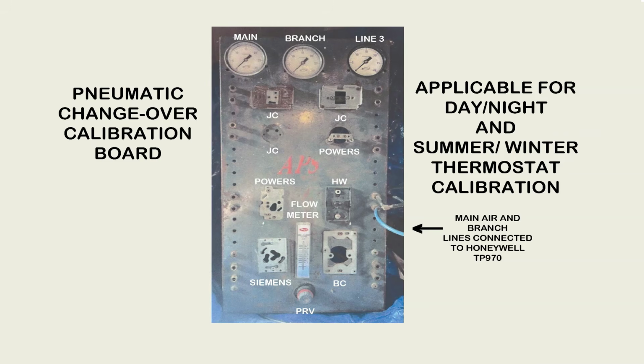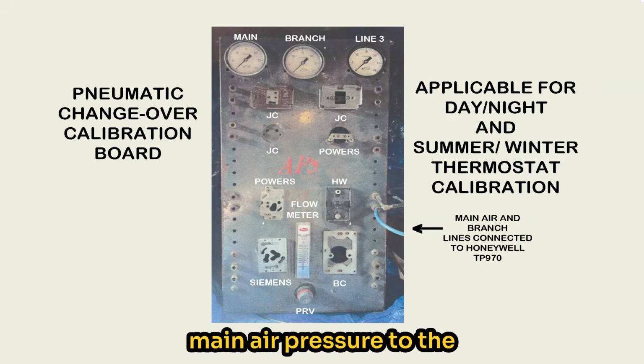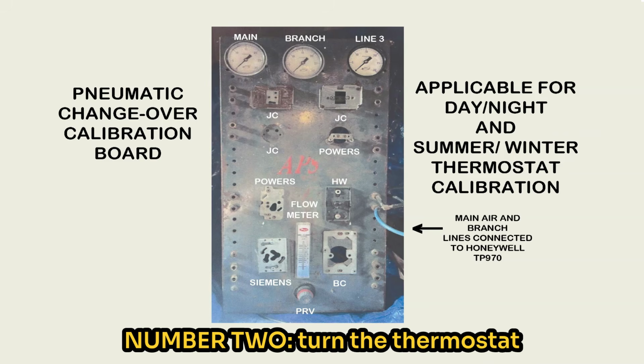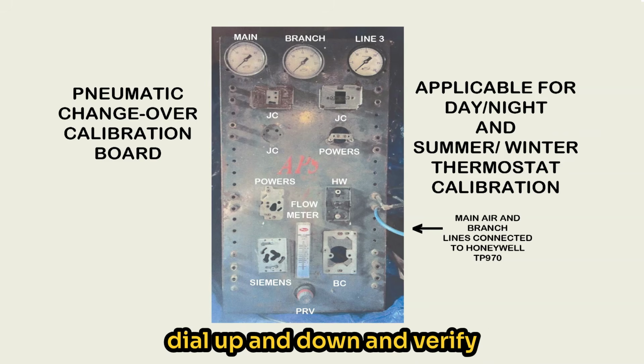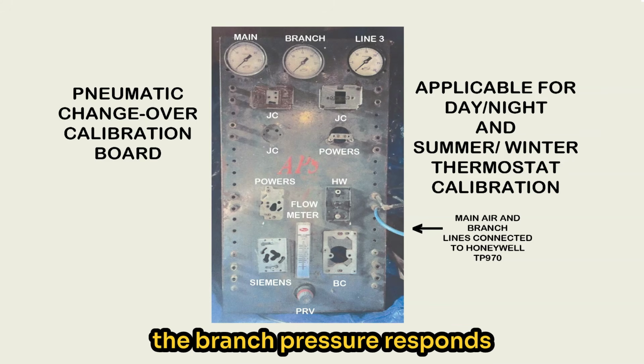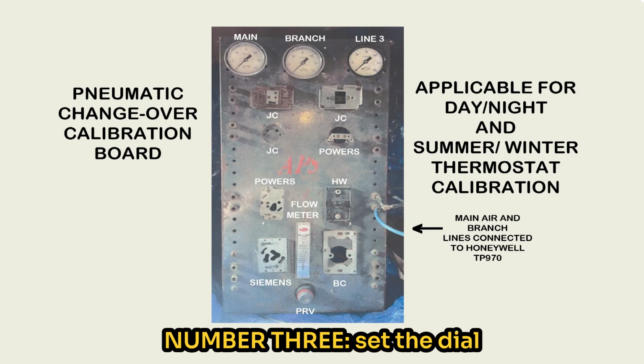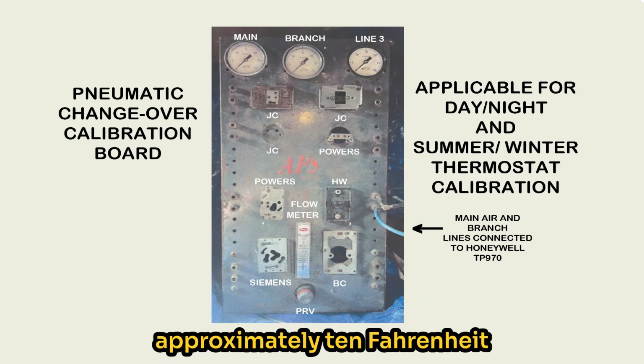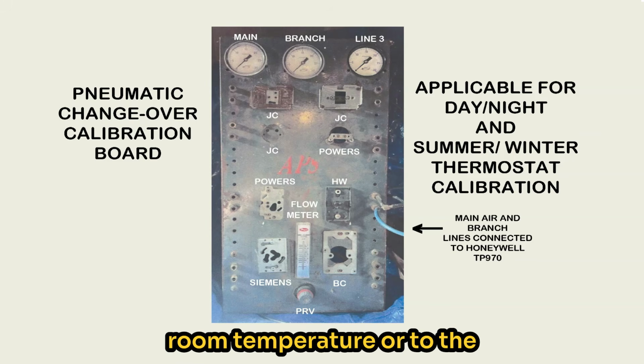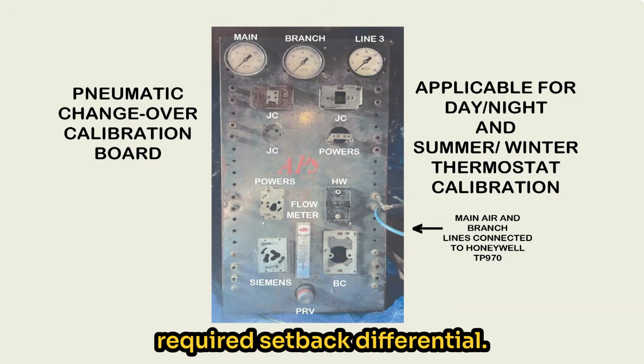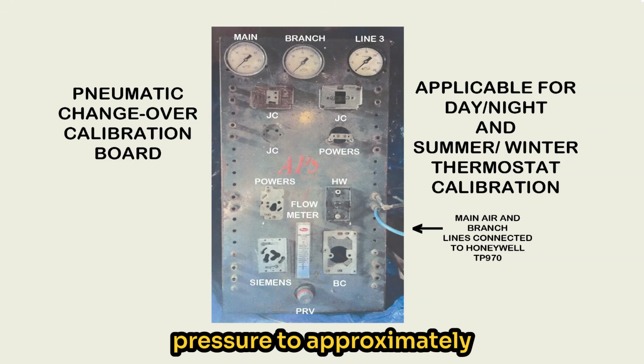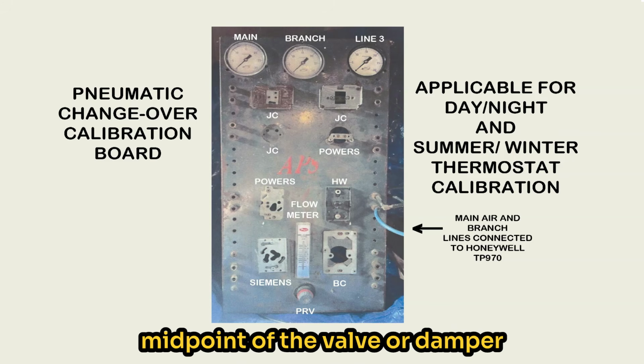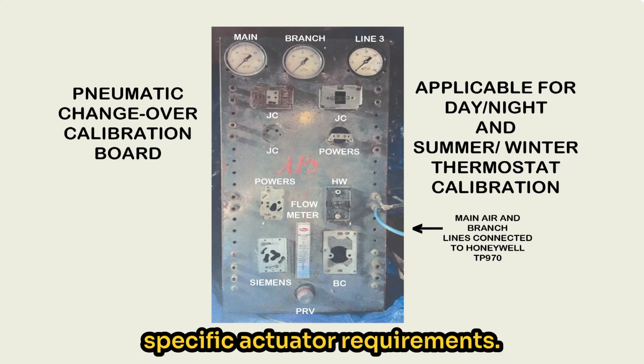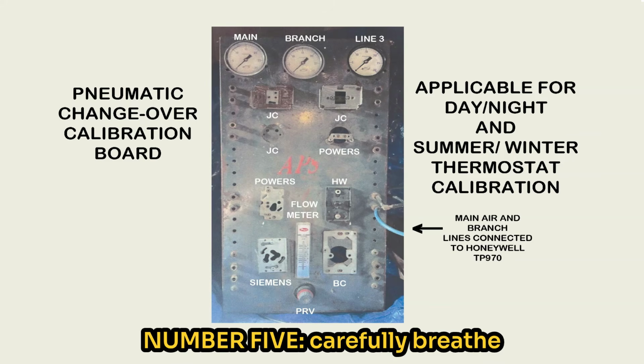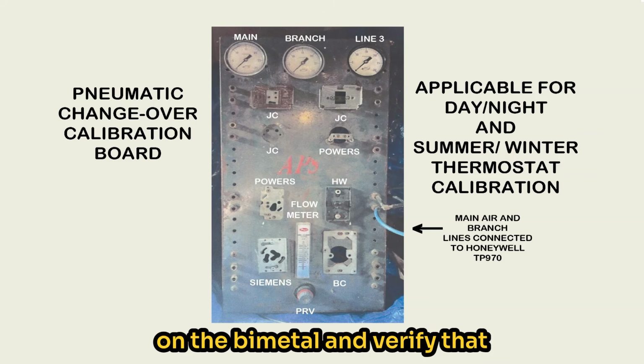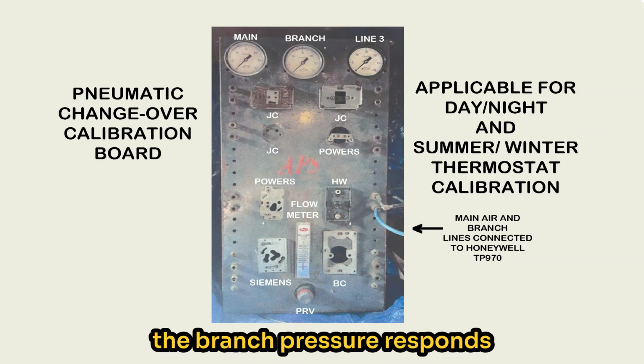Calibrating the night setting. Number 1, set the main air pressure to the night mode pressure. Number 2, turn the thermostat dial up and down and verify the branch pressure responds through the appropriate ranges. Number 3, set the dial approximately 10 Fahrenheit degrees above the actual room temperature or to the required setback differential. Number 4, adjust the branch pressure to approximately midpoint of the valve or damper stroking range, or according to the specific actuator requirements.